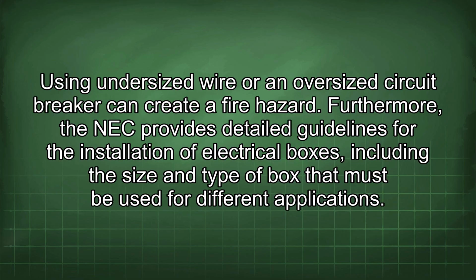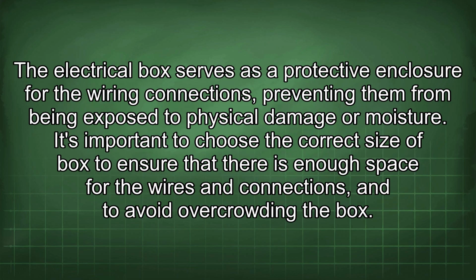Furthermore, the NEC provides detailed guidelines for the installation of electrical boxes, including the size and type of box that must be used for different applications. The electrical box serves as a protective enclosure for the wiring connections, preventing them from being exposed to physical damage or moisture. It's important to choose the correct size of box to ensure that there is enough space for the wires and connections, and to avoid overcrowding the box.